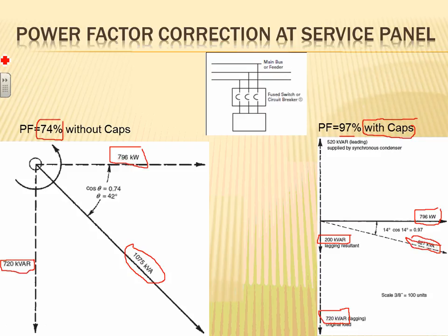So by adding a capacitor bank, capacitors are rated in capacitive kVAR. The system almost always has an inductive kVAR, and these are like day and night, positive and negative. When they join together, they neutralize each other. So if they're equal, you get zero. If they're not equal, you get the difference between the two, right? Everybody understand? My assumption is you guys are familiar with that one. And then you stick that capacitor in. Basically, here's my 200 kVAR, and I stuck my 200 kVAR right into here, with a circuit breaker coming out of the switchgear, with a little bank box, with a conduit and a wire, and you tie it to your capacitor bank.